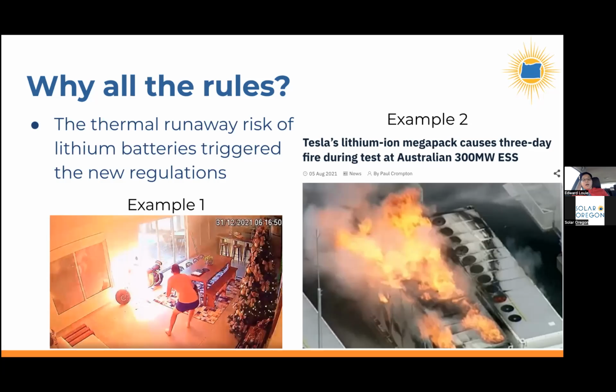Another way that batteries start to catch fire is due to a defective charging controller that allows the cells to be overcharged. A working charge controller will monitor the voltage to keep the voltage of the individual cells from getting overcharged. And additionally, the battery management system has temperature sensors peppered throughout the cell pack. And if any of the cell regions reach a temperature above the safe limit, it'll stop charging. Those are the ways it normally keeps the lithium battery healthy and working correctly.